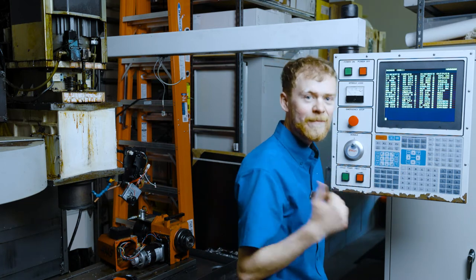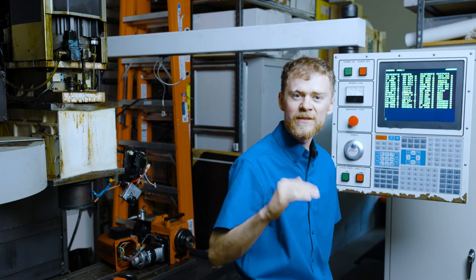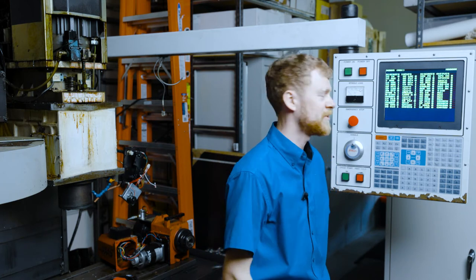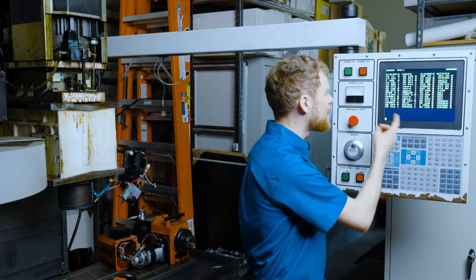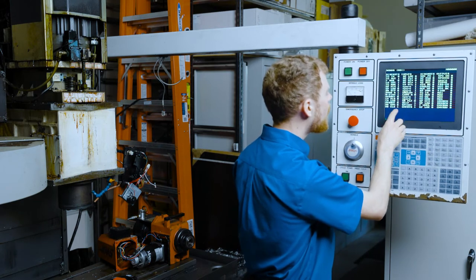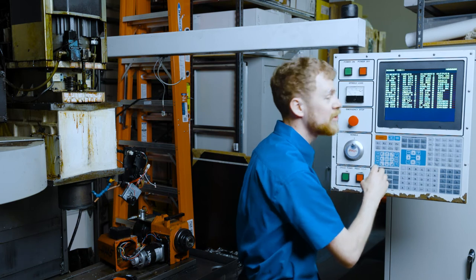Watch the diagnostics and verify that the piston is going down and the switches are changing state. On the screen, I saw the drawbar open and drawbar closed switch change.